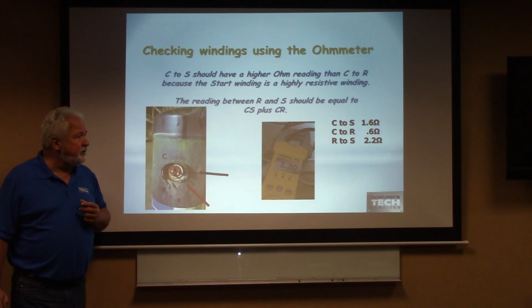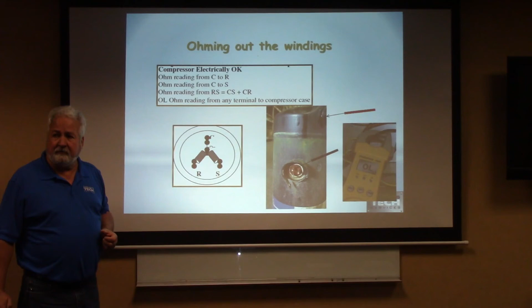All right, so if everything's ohming out correctly, I should have an ohm reading from common to run. I should have an ohm reading from common to start. The ohm reading from run to start should be the combination of both of those. Yes? Good. And there should be an OL reading from any terminal to the compressor case. Any one of those to the case, I should have a lot of ohms. I should have no path for current to flow from any one of those to the case. So touching there, touching to the case, I should see OL, or a lot of ohms. Everybody good? Sweet. All right. What do we have here?